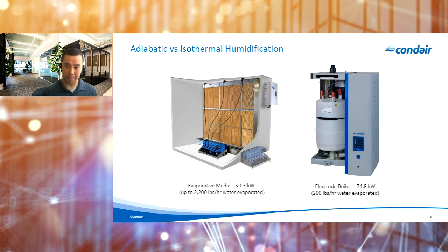And our general recommendation here is to look at or even consider adiabatic type systems for humidification loads or cooling loads over about 200 to 250 pounds an hour, which is really the point where they start to make sense economically, both from a CapEx and OpEx point of view. But again, here, the main consideration is if you're looking at this strictly for humidification and you don't necessarily need that cooling effect from an adiabatic system, you would need to consider either preheat or reheat requirements that may offset some of those potential energy savings moving to a cold water or adiabatic system.